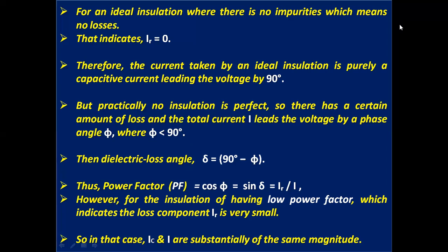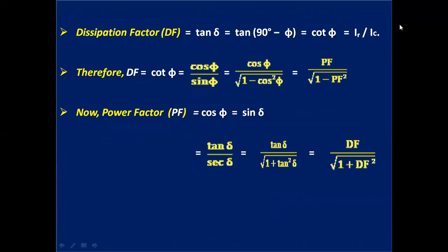However, for the insulation having low power factor, the loss component IR is very small. So, in that case, IC and I are substantially of the same magnitude. Now, dissipation factor equals tan delta, that is tan of 90 degree minus phi, that equals cot phi equals IR by IC. Therefore, dissipation factor equals cot phi, that is cos phi by sin phi equals cos phi over root of 1 minus cos square phi. Therefore, it is the power factor divided by root of 1 minus power factor square.